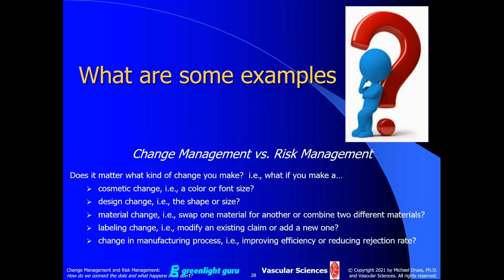It's not real specific as to the degree, that's up to us, but some information about the manufacturing process. It's not, at least not yet, in the 510K regulation. We have had discussions at FDA about putting it in there, and I think overall it is a good idea to put it in there because, let's be honest, even in the sub-class 3 universe, even in the class 2 and below universe, in 510Ks and de novos, our technologies are becoming more complicated. Our manufacturing processes are becoming more complicated.